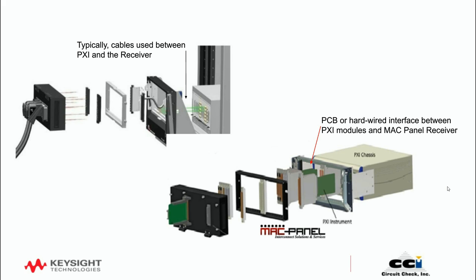On the lower right is a method that uses off-the-shelf interposer boards made of PCB materials that directly connect the PXI module instrumentation to the receiver. This helps ensure conductivity, repeatability, and helps eliminate RF interference. These are off-the-shelf modules, or they could be easily custom-made.